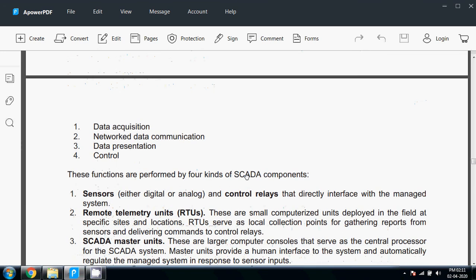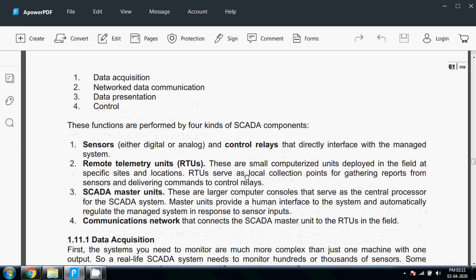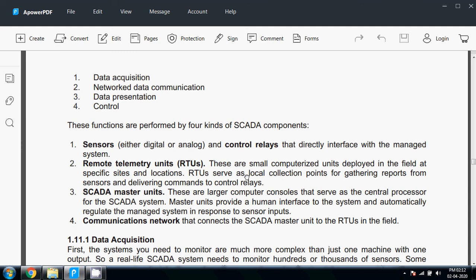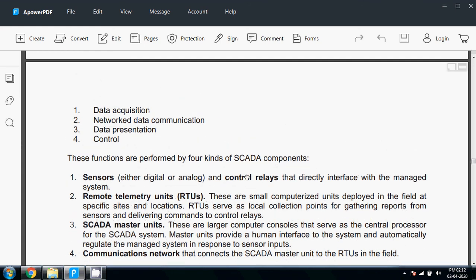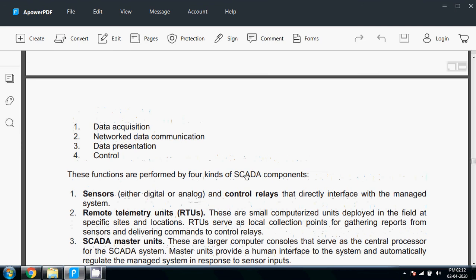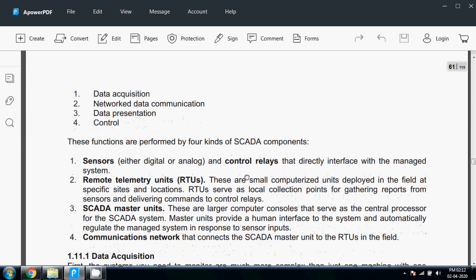SCADA has main components: sensors and control relays are the main components of SCADA systems. Remote Telemetry Units (RTUs) are small computerized units deployed in the field at specific sites and locations. RTUs serve as collection points for gathering reports from sensors and delivering commands to controls. SCADA master units are larger computer consoles that serve as the central processor for the SCADA system. Master units provide a human interface to the system and automatically regulate the managed system in response to sensor inputs. Communication networks connect the SCADA master units to the RTUs in the field.